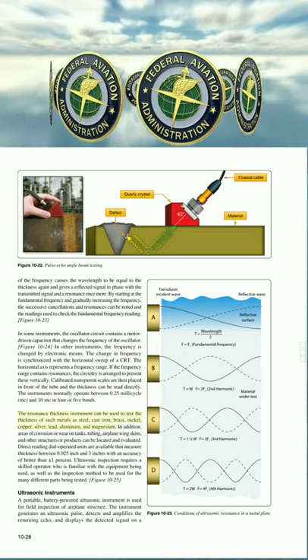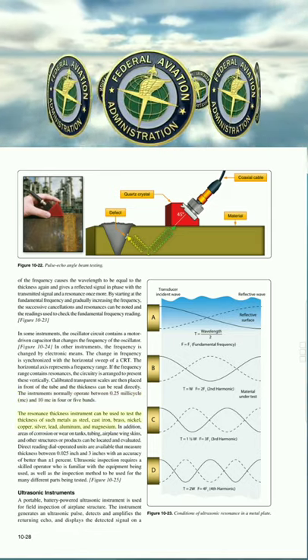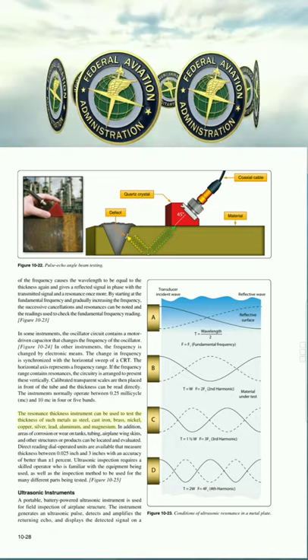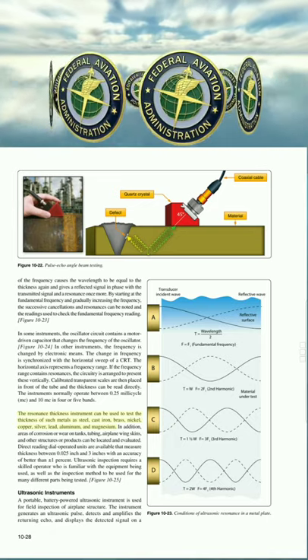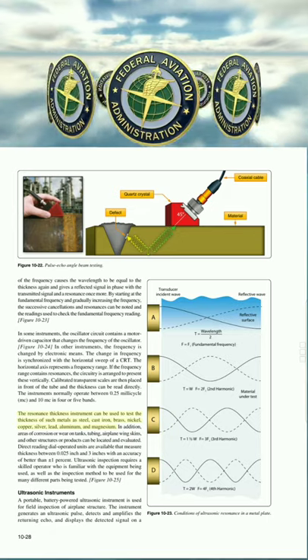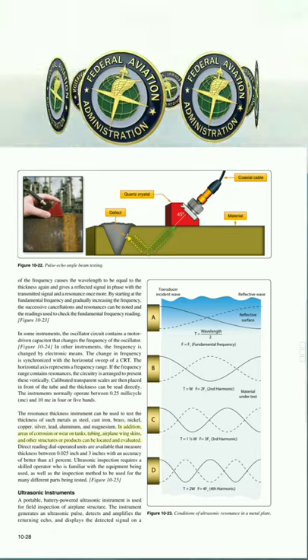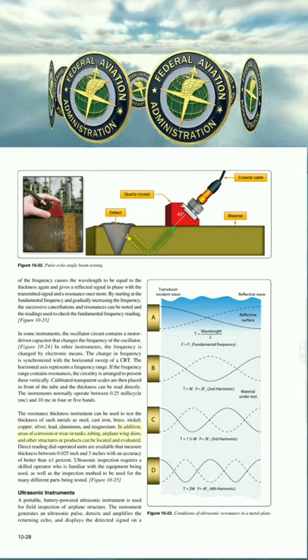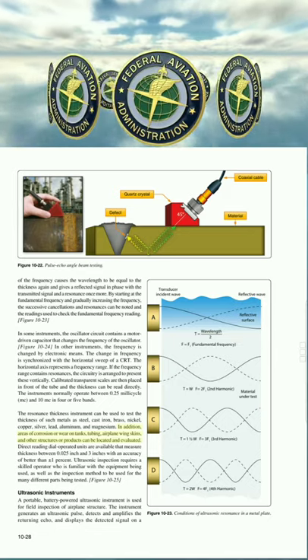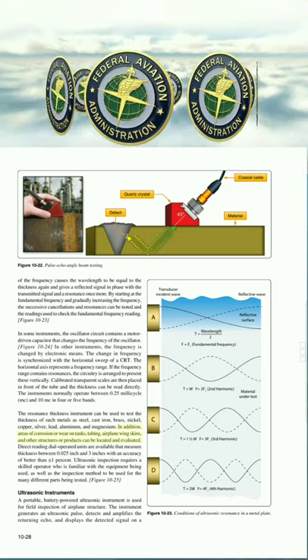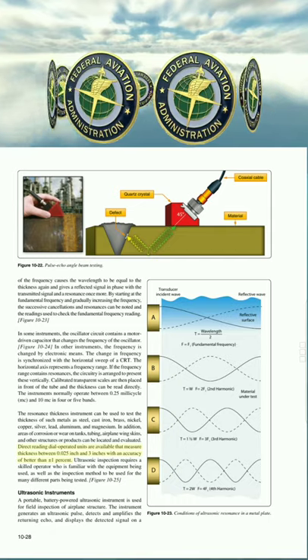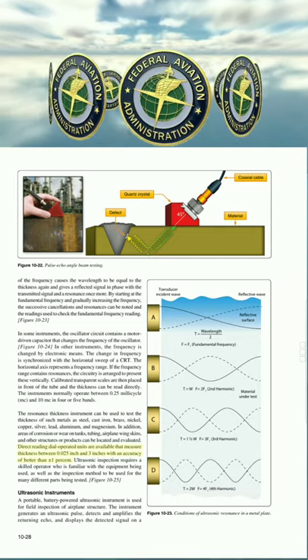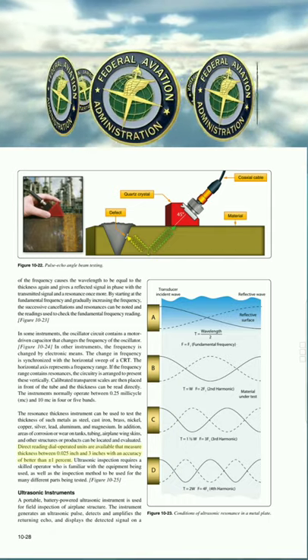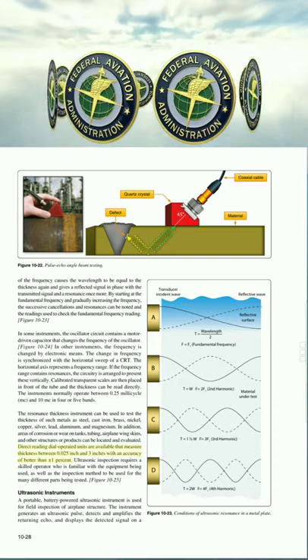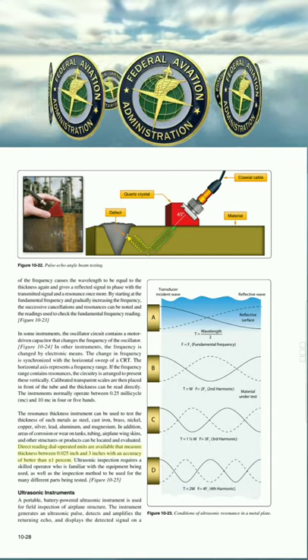The resonance thickness instrument can be used to test the thickness of such metals as steel, cast iron, brass, nickel, copper, silver, lead, aluminum, and magnesium. In addition, areas of corrosion or wear on tanks, tubing, airplane wing skins, and other structures or products can be located and evaluated. Direct reading dial operated units are available that measure thickness between 0.025 inch and 3 inches with an accuracy of better than plus or minus 1%.